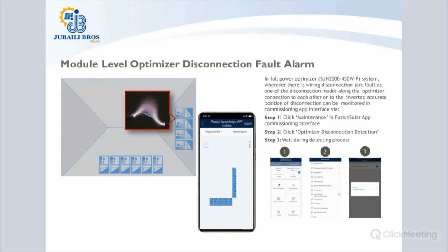And again, one of the most beautiful advantages of a PV optimizer is in detecting arcs at the module level. Remember, the majority of the PV inverters that are coming up now have arc fault detection facilities, so they can detect arc faults, but most of them detect the arc fault at the string level. So, for example, with Huawei PV optimizers, when an arc is detected at the string level, the signal is sent to the PV inverter, and then the string can shut down.